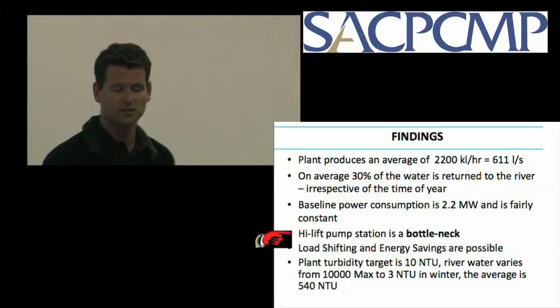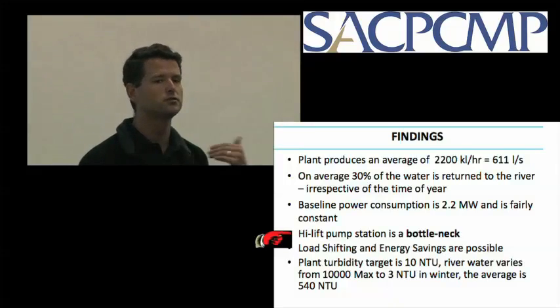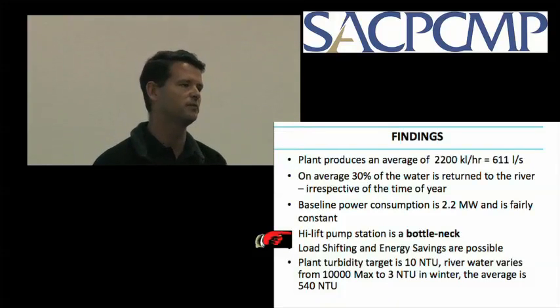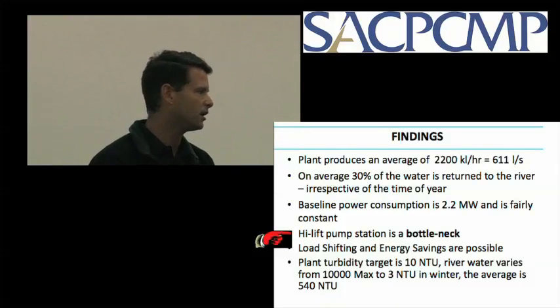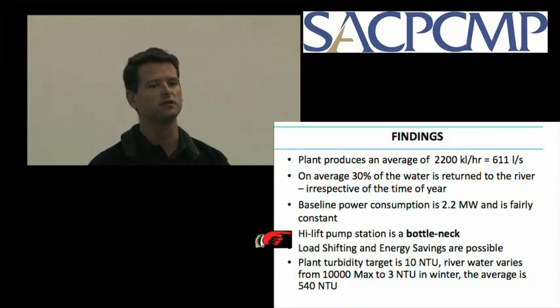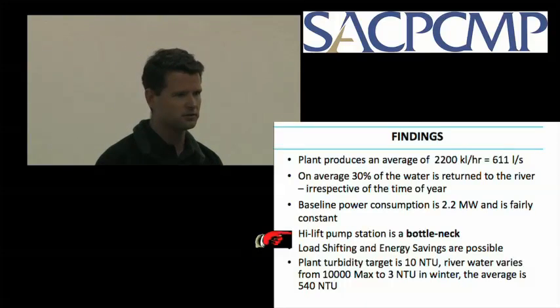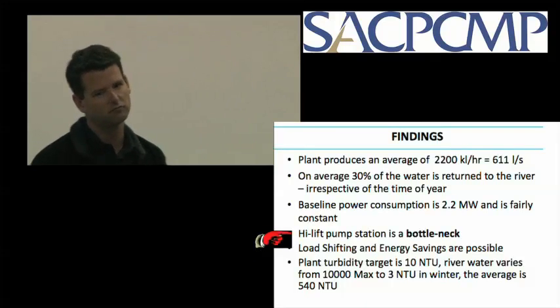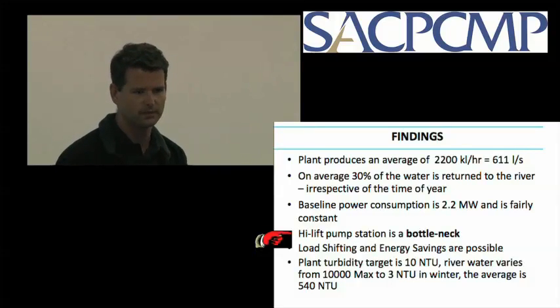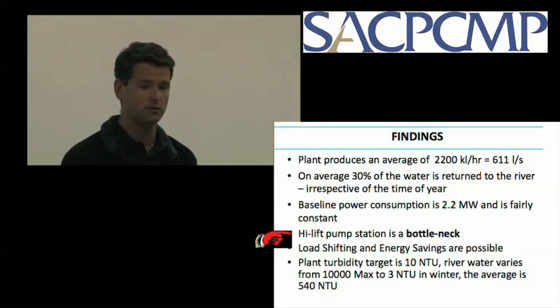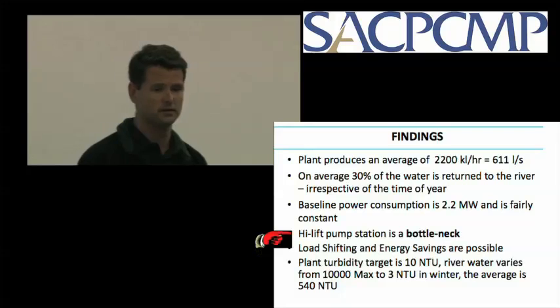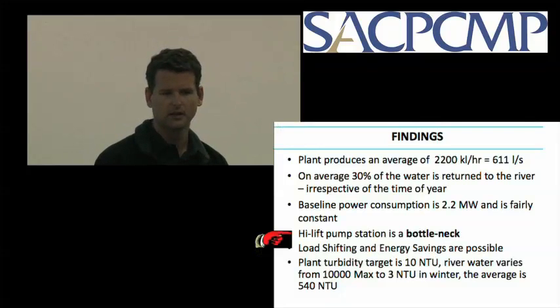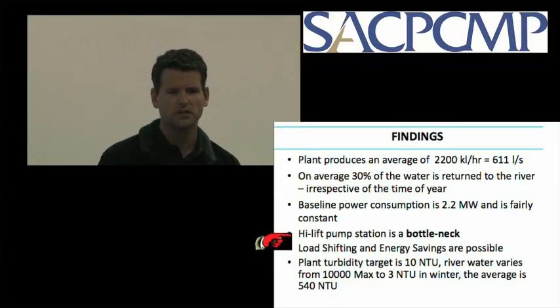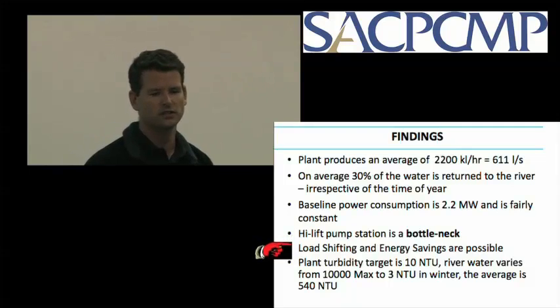The high lift pump station was a bottleneck, so if we wanted to stop the plant, we did not have enough pumping capacity to catch up in the 2 hours that we wanted to stop, and maybe even the 4 hours, because peak periods are from 7 to 10 in the morning and from 6 to 8 at night, when you're suddenly paying sort of double for your electricity. So it's very cost effective to stop a plant, if you can during those periods. The load shifting and energy savings were possible, and I'll go into that in more detail.